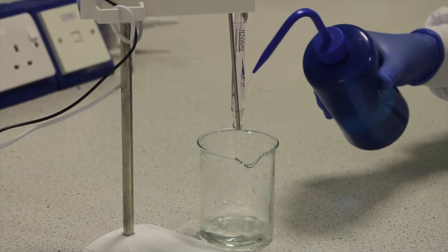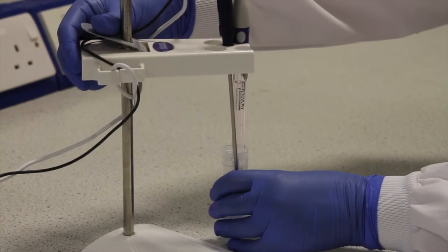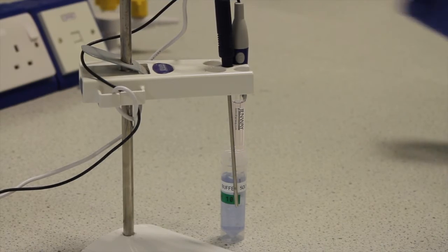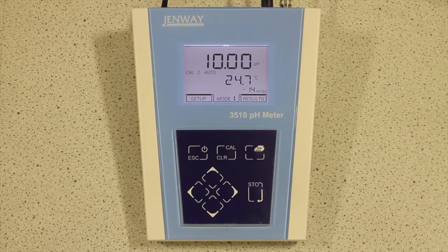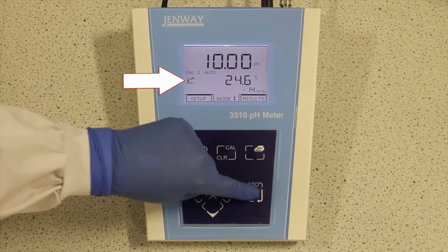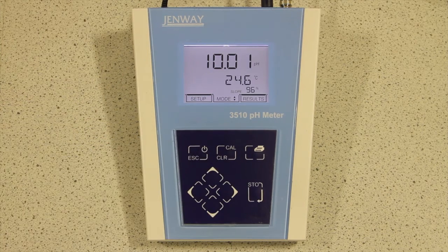The electrode is rinsed and placed in the pH 10 buffer. As before, once the reading stabilises and the endpoint symbol is displayed, press the STO button and the display will update. The pH meter is now calibrated to measure the pH of a solution in the alkaline range.